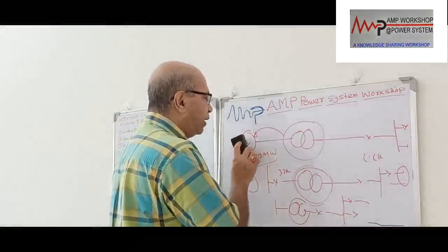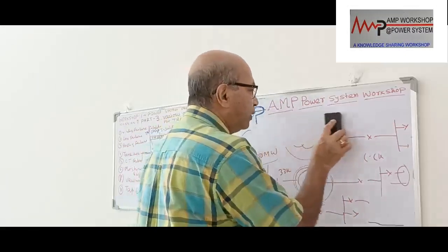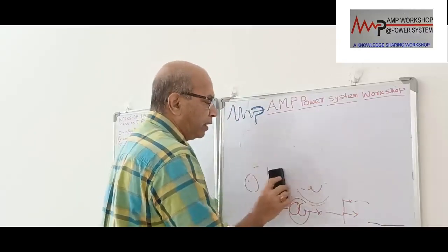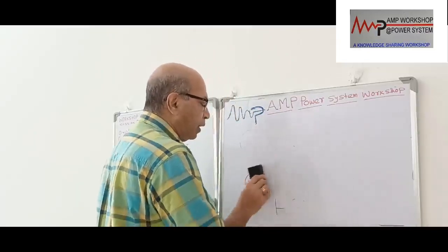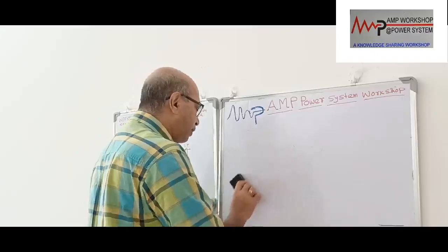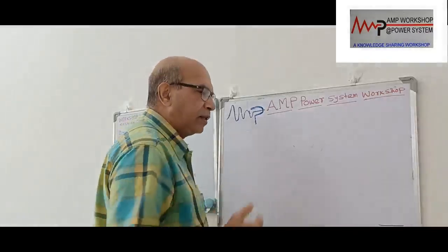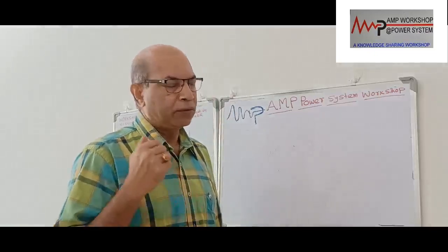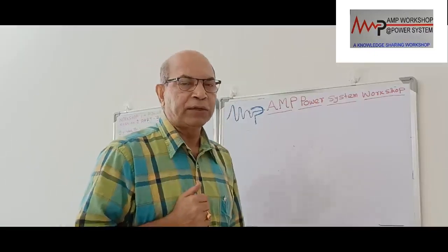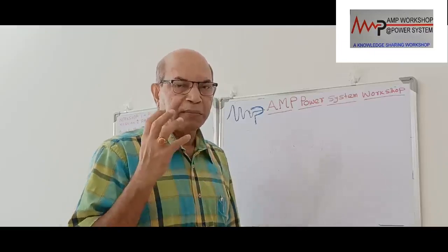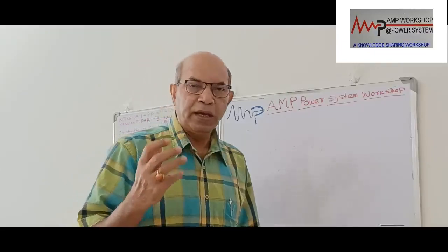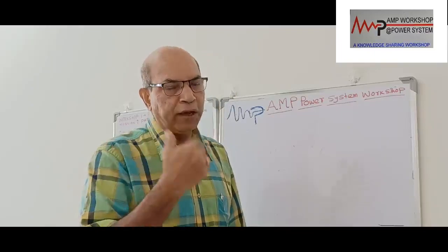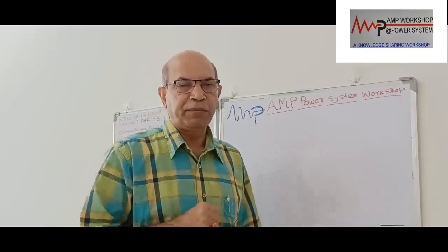These are the 3 points I discussed. But in addition to this, there are major drawbacks. If there is a transformer failure, a major issue is that the transformer is the heaviest piece of equipment. Depending on the size, it can weigh about 100 ton, 80 ton, 50 ton. So in that case, with heavy weight transformers to handle, if there is a minor failure, it may get repaired at site itself by mobilizing the OEM representative or the manufacturer representative.